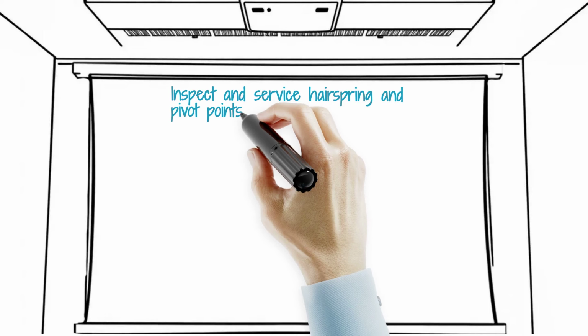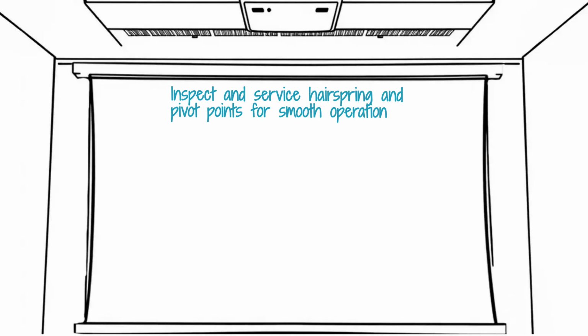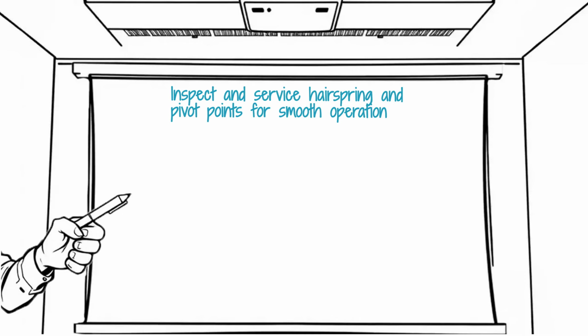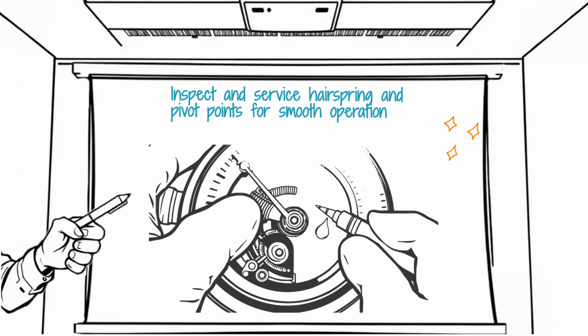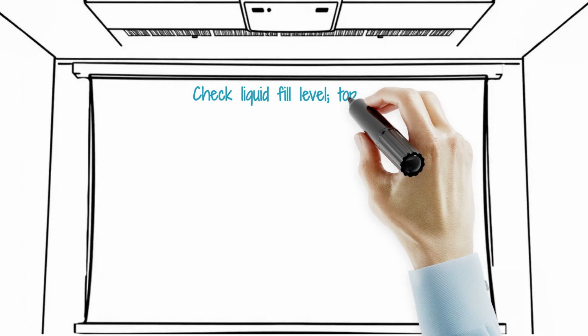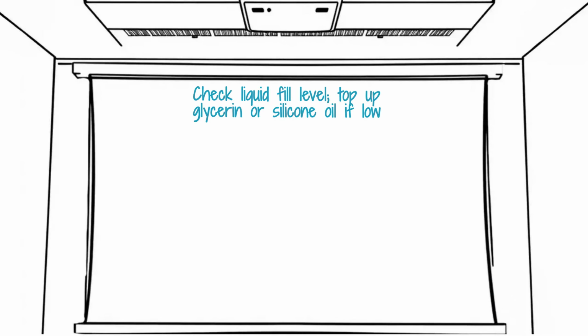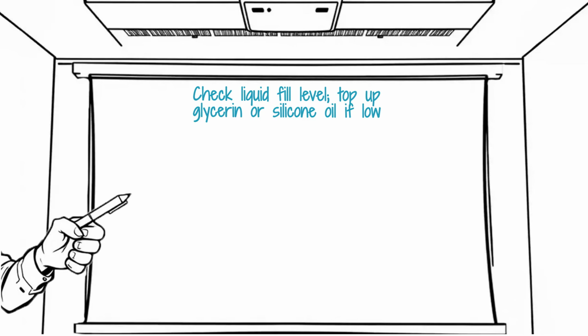While the gauge is open, inspect the hairspring for tension and cleanliness, because a dirty or tangled spring will cause the pointer to jump or lag during pressure changes. Apply a tiny drop of watchmaker's oil to the pivot points if the movement feels stiff. If the gauge is liquid-filled, check the level of the glycerin or silicone oil and top it up if necessary, as this fluid dampens vibrations and protects the internal gears from wear.